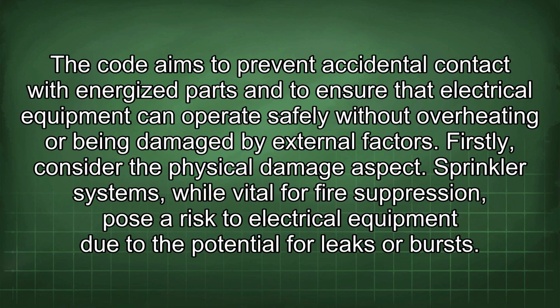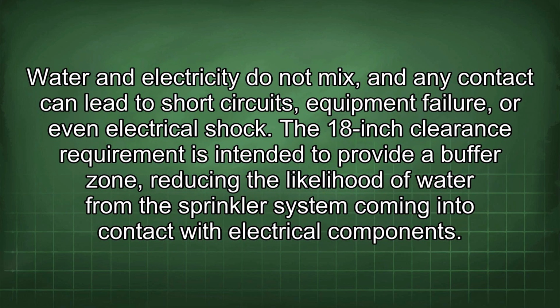The code aims to prevent accidental contact with energized parts and to ensure that electrical equipment can operate safely without overheating or being damaged by external factors. Firstly, consider the physical damage aspect. Sprinkler systems, while vital for fire suppression, pose a risk to electrical equipment due to the potential for leaks or bursts. Water and electricity do not mix, and any contact can lead to short circuits, equipment failure, or even electrical shock. The 18-inch clearance requirement is intended to provide a buffer zone, reducing the likelihood of water from the sprinkler system coming into contact with electrical components.